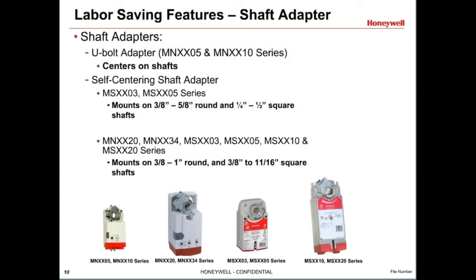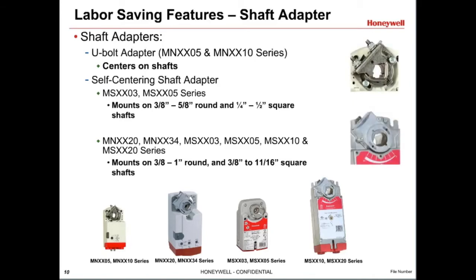Honeywell DCAs help save installation time and labor. On the MN5 and 10 Newton meter non-spring return actuators, that's 44 and 88 inch-pounds, Honeywell DCA shaft adapters have a U-bolt design. Many other actuators use a self-centering shaft adapter. These make it easy to tighten an actuator to the shaft with only one hand and center automatically onto the shaft. This is critical for applications with larger torque loads. In addition, these Honeywell shaft adapters can limit actuator travel in 5-degree increments.